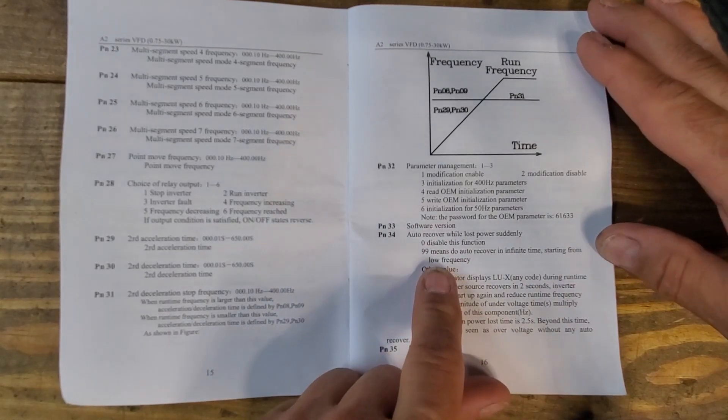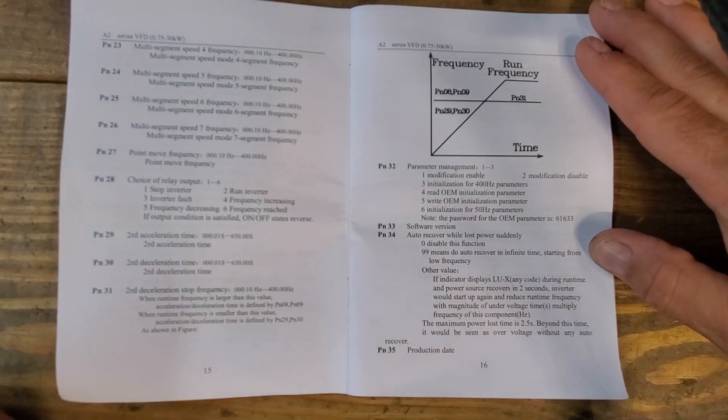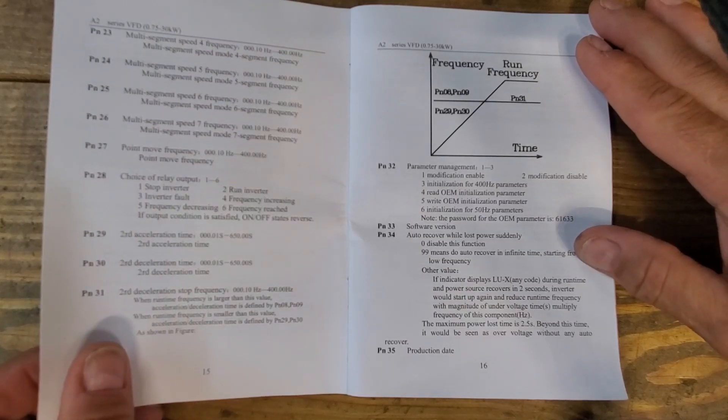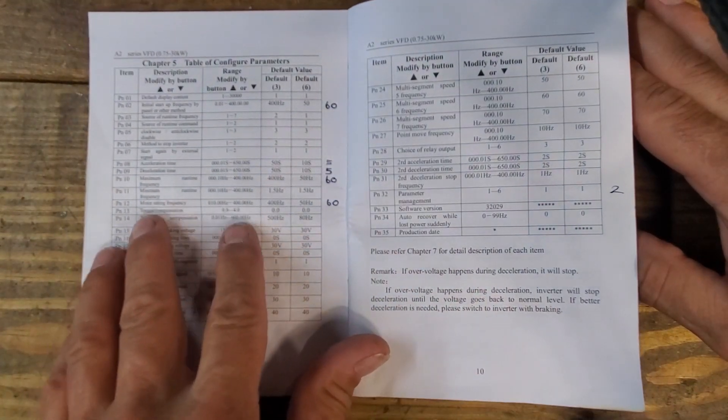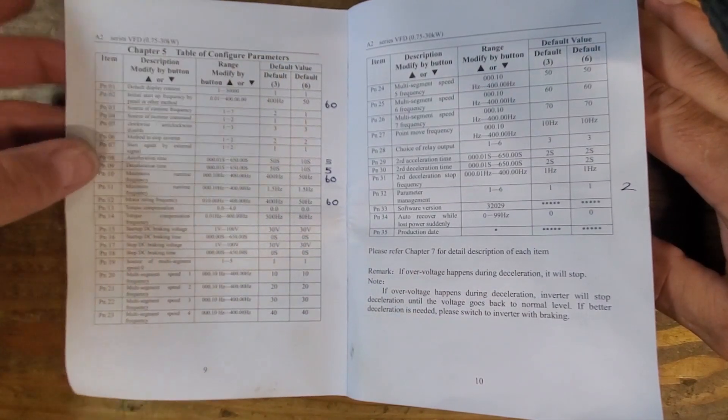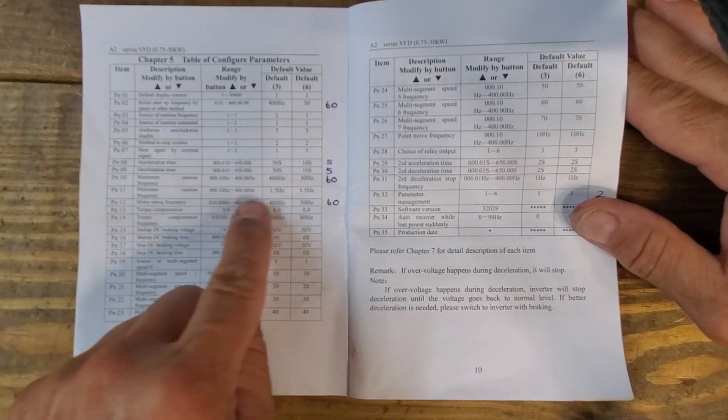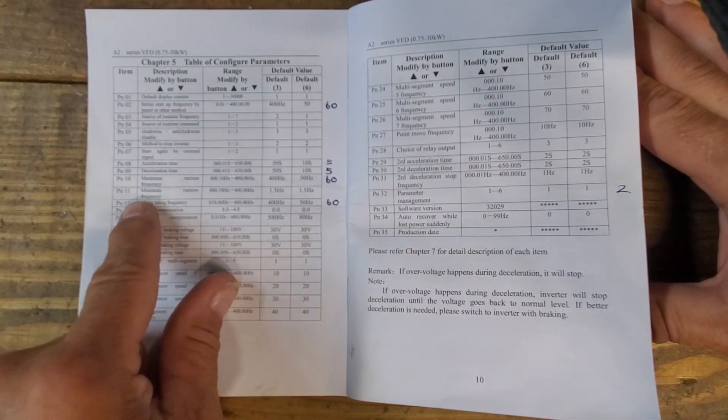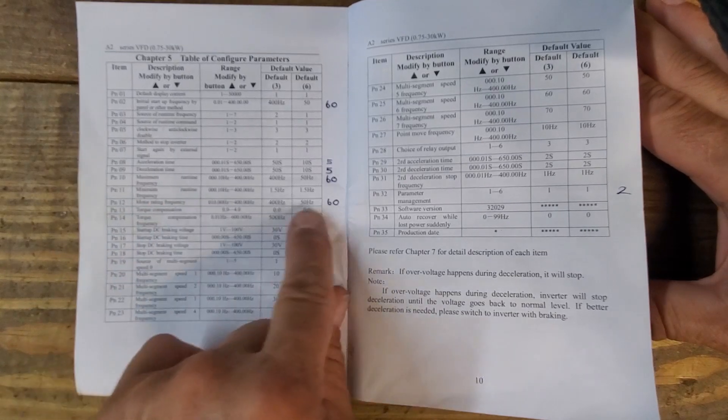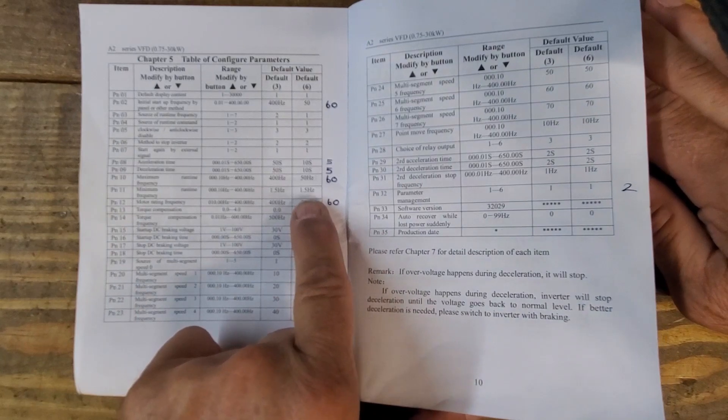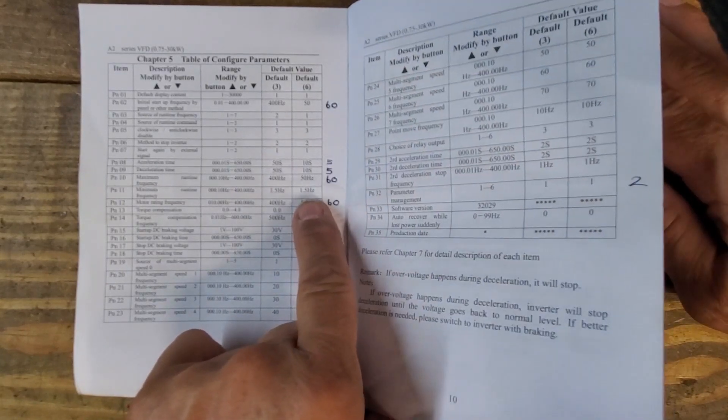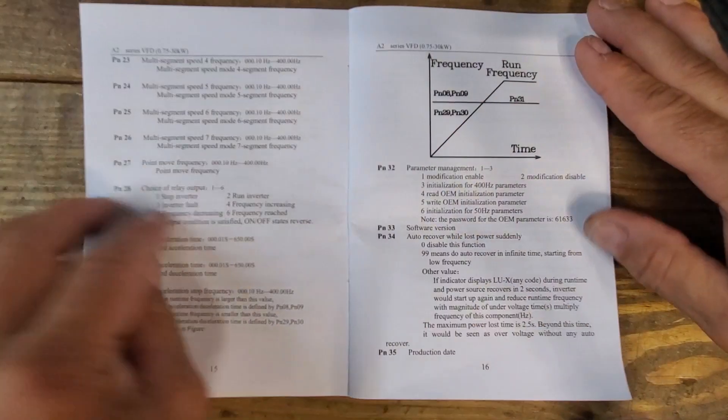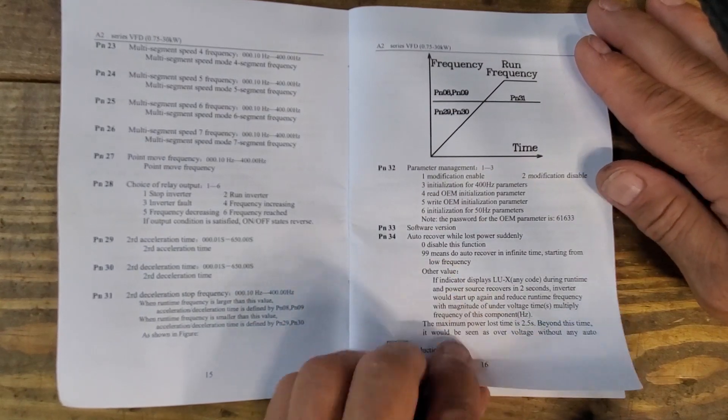It also states that if you set it to 99, the auto recover will happen with an infinite time starting from the low frequency. Mine does not do that. I've actually tried that and set it, and it didn't make any difference. It's possible that the reason it's not doing anything is that my minimum runtime frequency is set to 1.5 Hertz. So when it initializes, it may come back on at 1.5 Hertz. I need to look at that and find out if I change that to 60 Hertz, whether on power failure set to 99, it will come back on to speed.